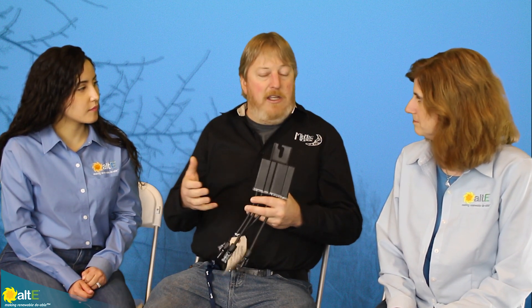When the receiver doesn't get the heartbeat, it will shut everything down. There are both AC and DC transmitters, because some grid-tie inverters have a 12-volt rail we can attach to. We connect the transmitter to the inverter's power source — either AC or DC — so that when the grid fails or you shut off the inverter disconnect, the transmitter will quit transmitting. If the device doesn't hear that keep-alive signal for about 10 seconds, it will shut off and assume it's supposed to go into rapid shutdown. So everything is fail-safe.